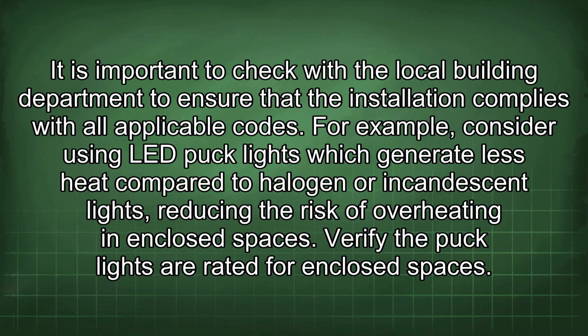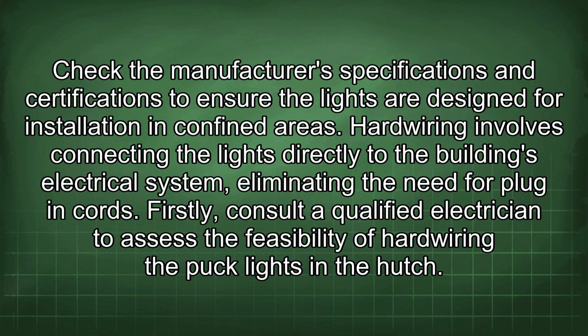with all applicable codes. For example, consider using LED puck lights which generate less heat compared to halogen or incandescent lights, reducing the risk of overheating in enclosed spaces. Verify the puck lights are rated for enclosed spaces. Check the manufacturer's specifications and certifications to ensure the lights are designed for installation in confined areas.